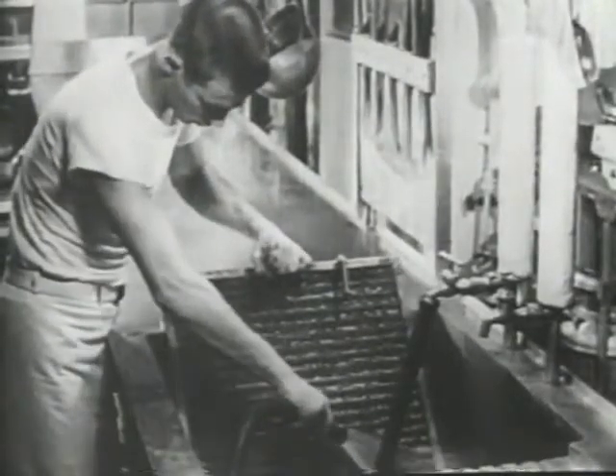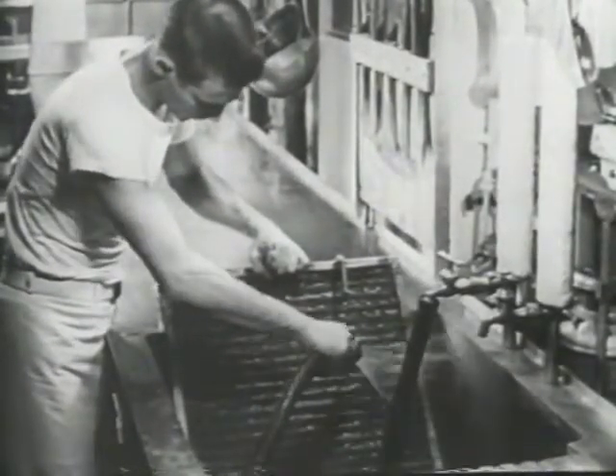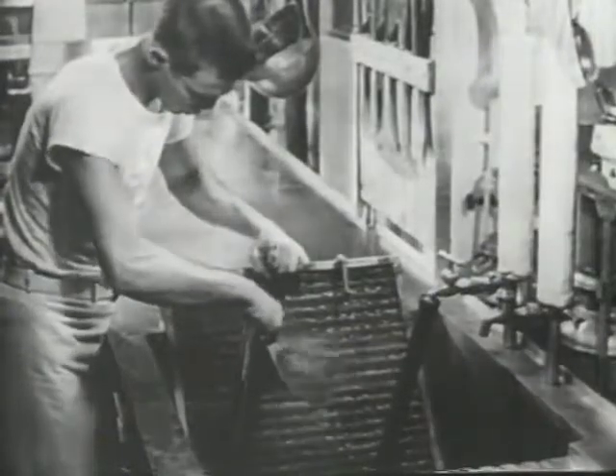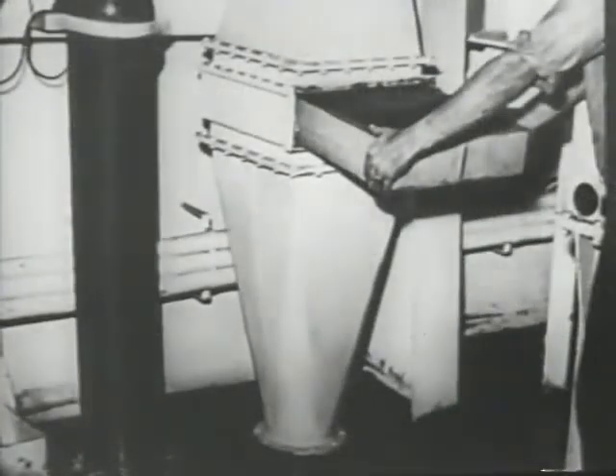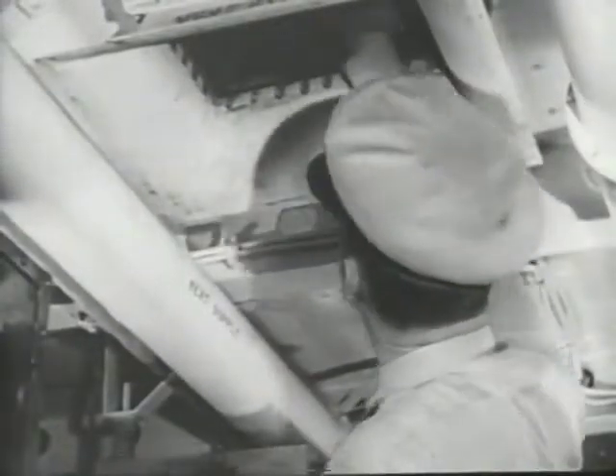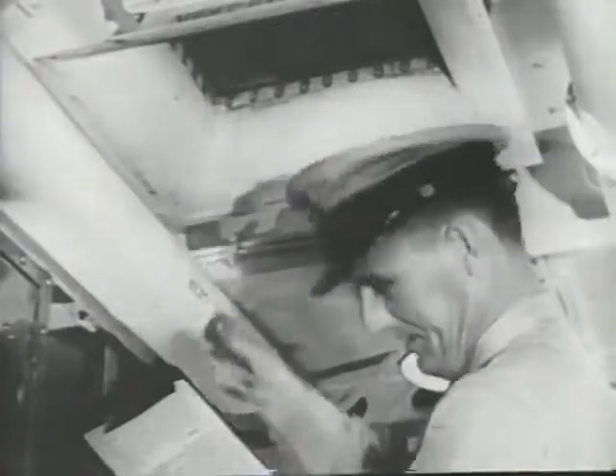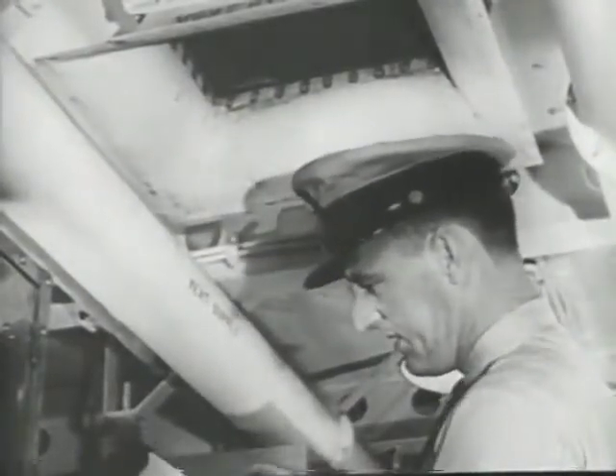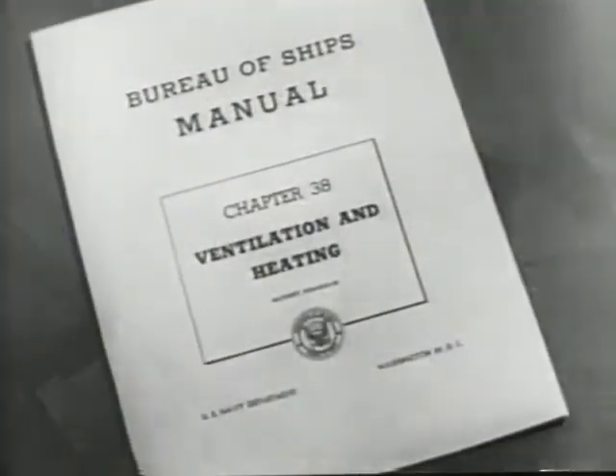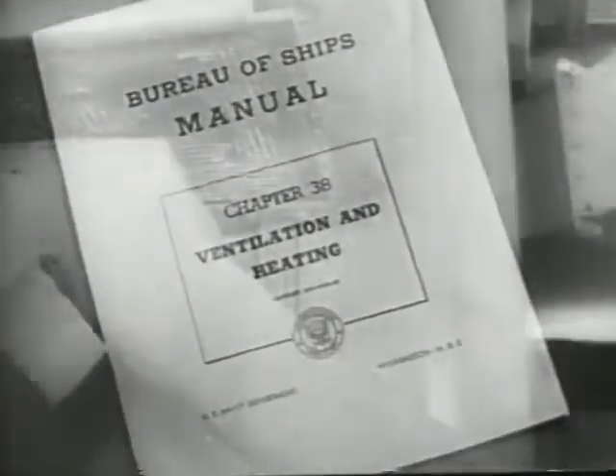Also, serious fire hazards are created by clogged grease filters in galleys, by dirty filters ahead of flame arresters, and by dirt accumulations in ducts. It is essential that each ship set up a definite schedule of inspection and maintenance as recommended in Chapter 38 of the Bureau of Ships Manual.